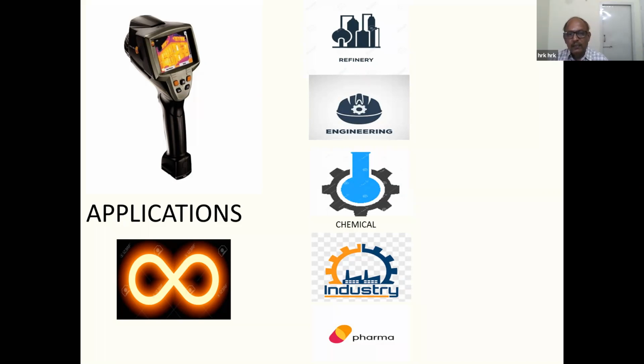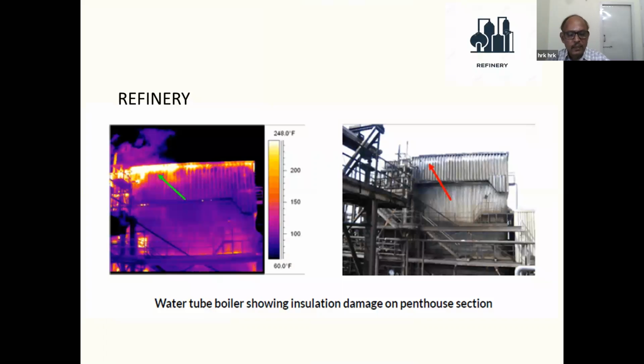Now we will see some applications of the thermal imager in refinery, engineering, chemical, and pharma industries. This thermal image was taken on a water tube boiler, where a hot spot is visible in the penthouse area as a bright spot, showing a temperature on the scale of more than 200 to 250 degrees, around 220 degrees. In this case, steam is leaking, resulting in loss of steam and loss of energy.